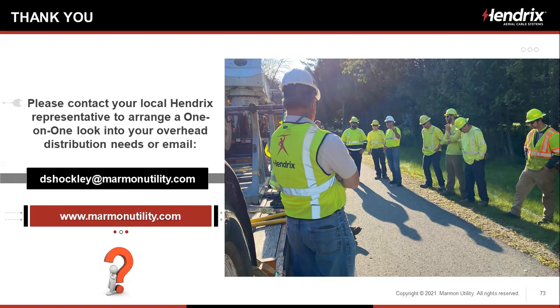Thank you. And you mentioned that there's an increase in spacer spacing to 50. It seems like with more weight, you may want to stay at 30 or maybe even reduce. So what's the reason for the increased spacing? The reason is that, number one, we would like to go up to 50 or 60 or 70 feet if we could, but we don't want conductor clashing. So there was a limit where we could say, okay, we're going to have some blowout on those individual phase conductors, and they're still not going to connect with each other if we go out to 50 feet, but maybe 60 feet would be too much.